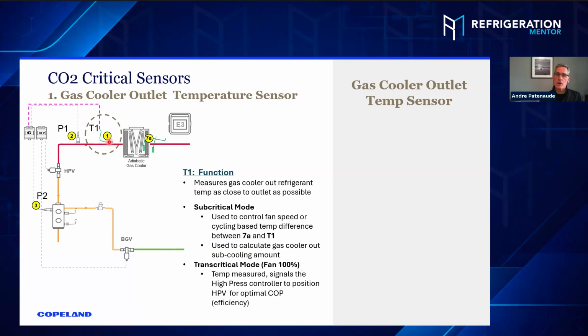Well, when it's not in subcritical, it's in transcritical mode. With our controls, when they hit 80 degrees ambient, fans are to be full speed, and we recommend fans to be at 100% full speed. So now it's sensing a transcritical gas cooler outlet temperature. Again, the high pressure control indicates to the valve, okay, now you need to position yourself at an optimal pressure for efficiency's sake. If it's measuring 95 degree gas cooler out, it's going to try to maintain a pressure of about 1,300 pounds. That's its optimum COP, coefficient of performance. If that temperature in the middle of the day goes up to 100 degrees, it's going to try to maintain 1,340 pounds. So these are integrated. Okay, so that's what it does.